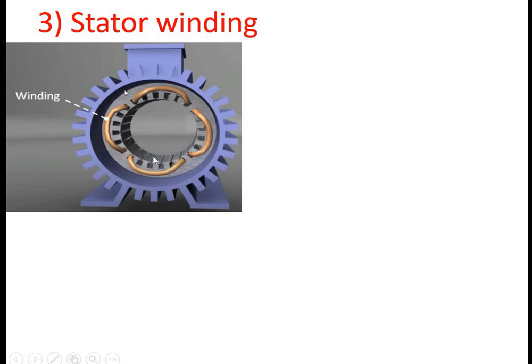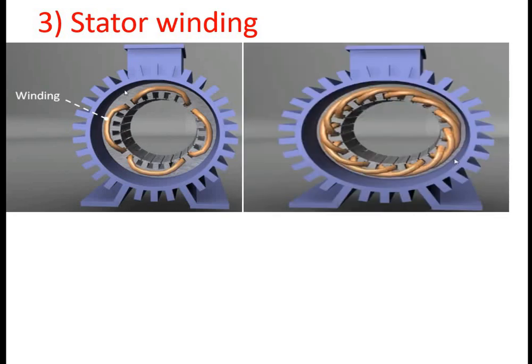So we are going to distribute the windings. For a single phase we are going to have a single winding, and that winding is going to be distributed among the slots available inside the stator core. So this is for a single phase. In the second diagram we can see the entire winding arrangement inside the slots for all the 3 phases. After making such arrangements, we bring the terminals of the 3 windings out to a common box called the terminal box. The terminal box is available on the stator frame.